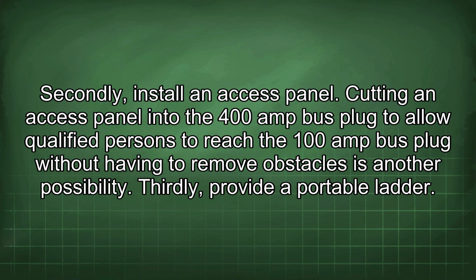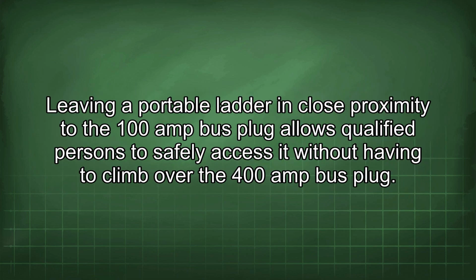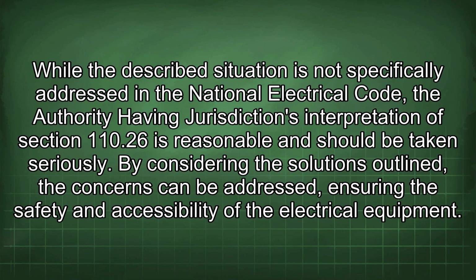Thirdly, provide a portable ladder. Leaving a portable ladder in close proximity to the 100 amp bus plug allows qualified persons to safely access it without having to climb over the 400 amp bus plug. While the described situation is not specifically addressed in the National Electrical Code, the authority having jurisdiction's interpretation of Section 110.26 is reasonable and should be taken seriously. By considering the solutions outlined, the concerns can be addressed, ensuring the safety and accessibility of the electrical equipment.